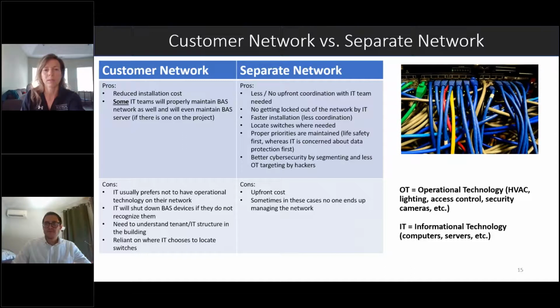Here's a really great question: can you combine various wiring strategies on the same install? Yeah, absolutely. A lot of times what I'll see is major systems, like maybe a chiller, where you really want to make sure that chiller is on its own wiring chain - you could do a home run wire to that chiller, and then all of your fan coils or anything else in the building could leverage something like the daisy chain wiring strategy. So you can definitely combine those wiring strategies as needed to make sure you're encompassing the system the way you want it.